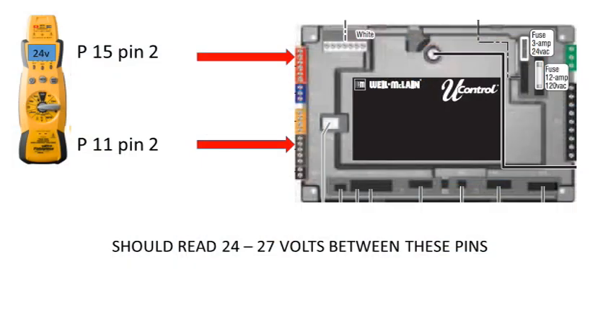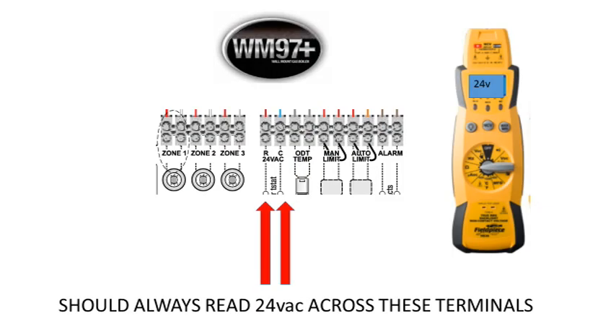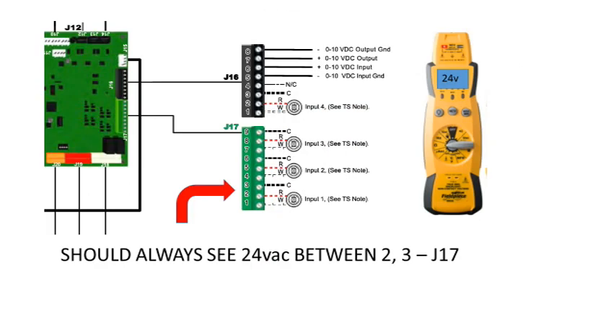Our last test here is to see if the control module itself is the issue. If the fuse is not blown, the transformer reads normal, and you still have a blank screen, it is possible the module has failed. With the power on, check to see if there is low voltage present between P15 pin 2 and P11 pin 2 on the Ultra or Evergreen. The 24 VAC low voltage pins on the WM97 or pins 2 and 3 on J17 for our Ecotech boiler. If we have confirmed the transformer is putting out low voltage and there is no reading on the low voltage terminals, the module has failed internally and will need to be replaced.